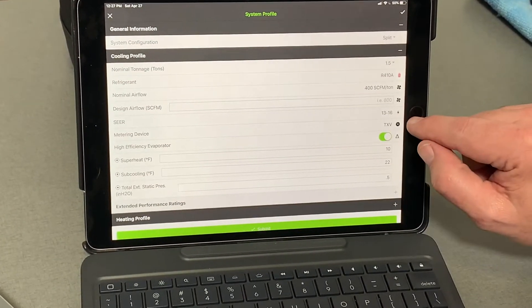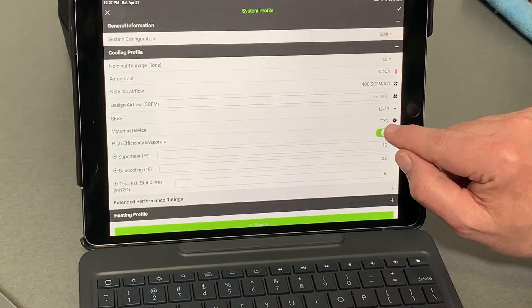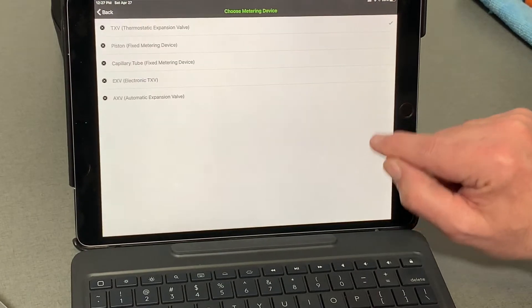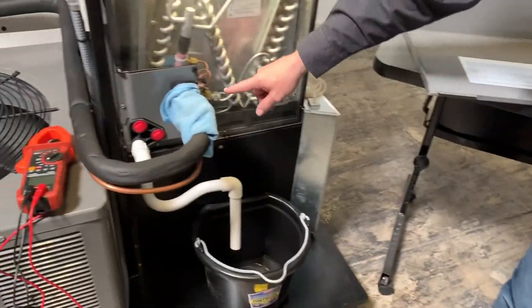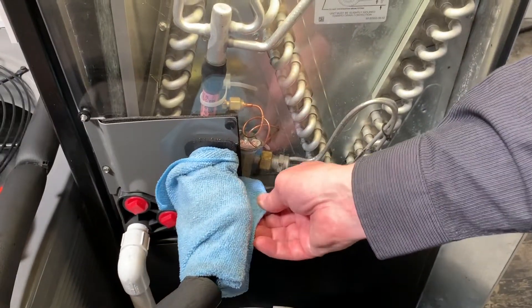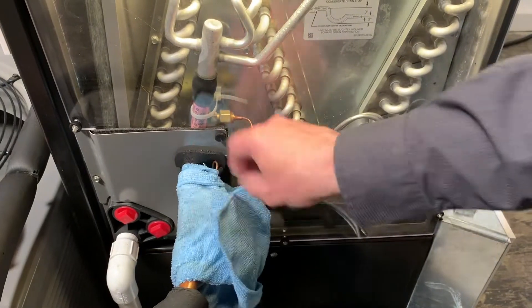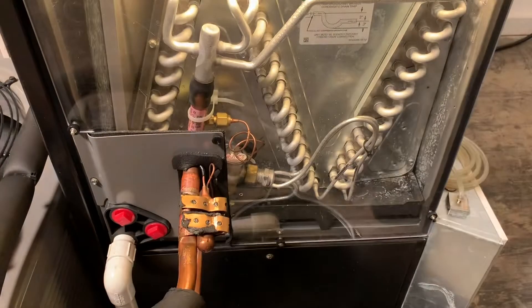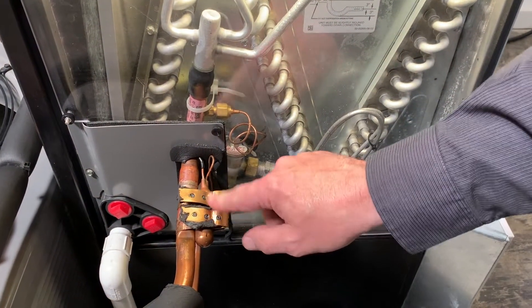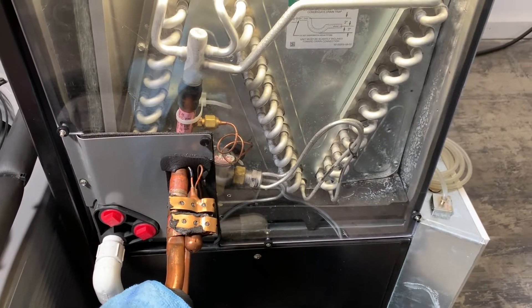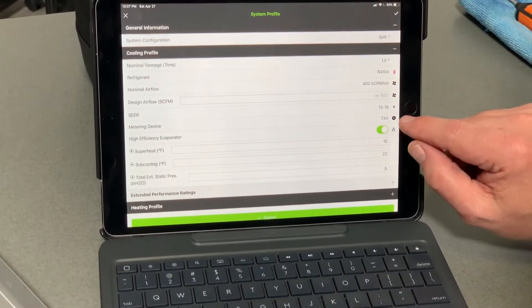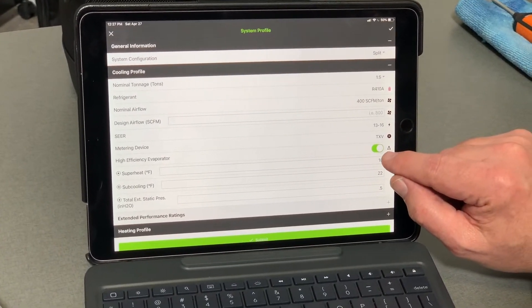Now for metering device, we need to know whether it's a TXV, fixed piston, or capillary tube. If we go over to this unit, you can see right here it has a TXV on there. I had the bulb wrapped with a rag just so it's not sweating in the shop, but obviously if you have a TXV bulb on the suction line, that's a TXV system. So I'll go ahead and select TXV — thermostatic expansion valve.